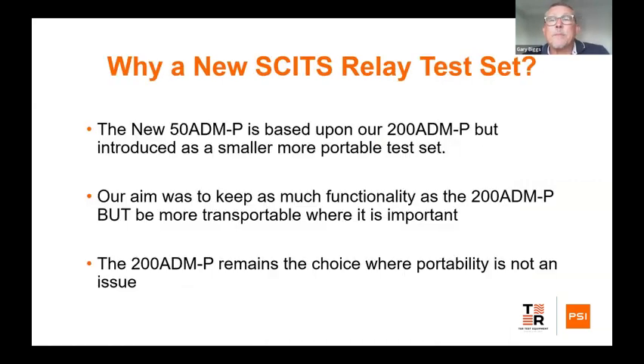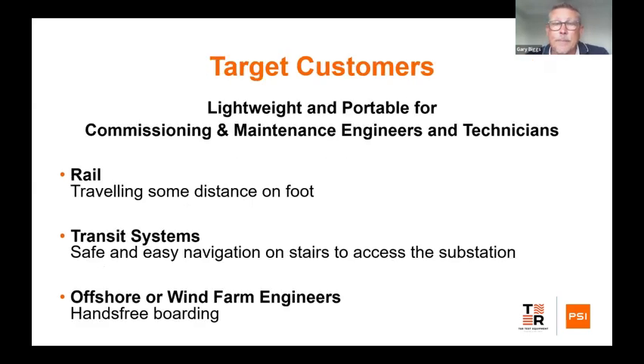So, as I said, the 50 ADM-P is based on our 200 ADM-P, but designed to be super portable. As you saw in that picture, it'll strap to your back. So if you're working in a situation where portability and lightness make a difference, this is an ideal solution. Our aim was to keep the functionality but be transportable and much lighter. The 200 ADM-P has a bigger size and a weight of around 26 kilograms, and we've managed to drop that right down to 15 kilograms or so. So that portability is a significant reason why we've introduced a newer relay test set.